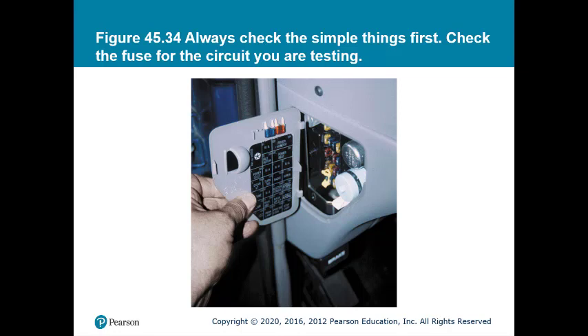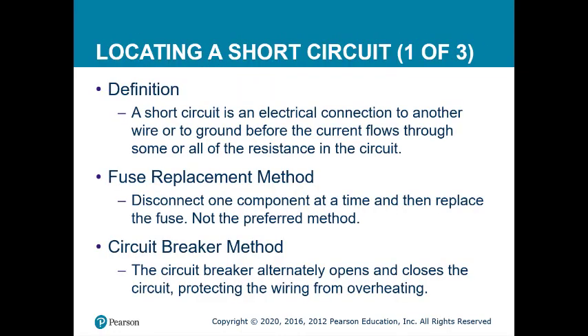In figure 45.34, it suggests to always check the simple things first, and I totally agree with this. Check the fuses for the circuit you're testing. If they're blown, that would indicate that there was some kind of high amperage event. High amperage events usually mean a short circuit. When it comes to locating a short, there are many different ways to do this. It can be difficult, but after you've done a few, they start to follow a pattern.